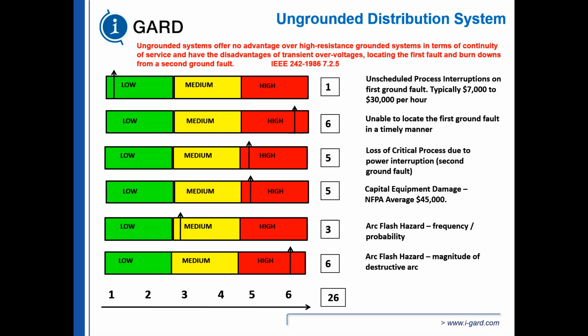So just to fill in those numbers again, unscheduled process interruptions are very low, so we're going to assign a 1 to that. Unable to locate the first fault: you cannot find the fault in an ungrounded system unless you start cycling breakers open and close. Remember I said those 3 lights are the same brilliance when you have a healthy system. So if you cycle the breaker open and the fault is downstream from that breaker, you're going to go from 2 bright lights and 1 light that's off, to 3 equally brilliant lights. And you'll determine that the fault is downstream from that location.